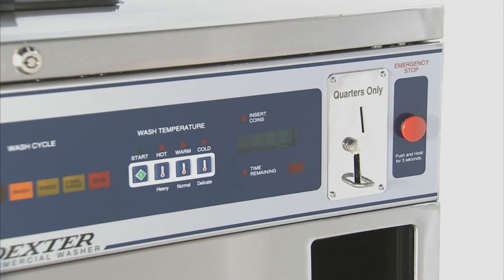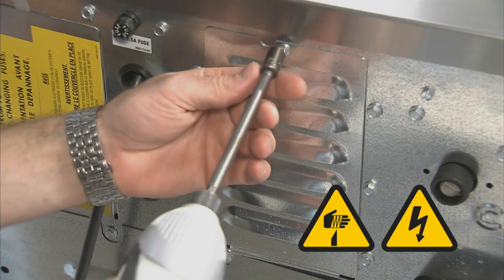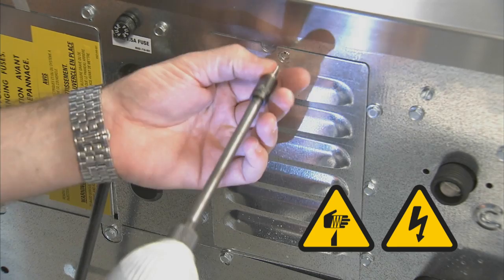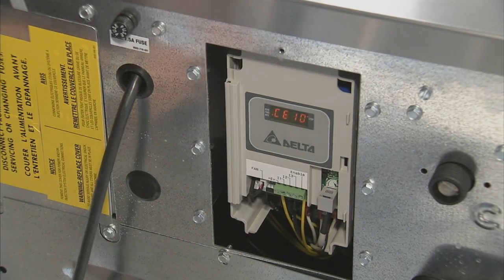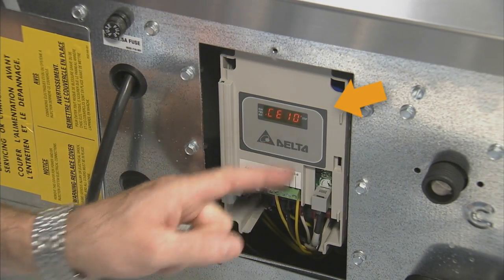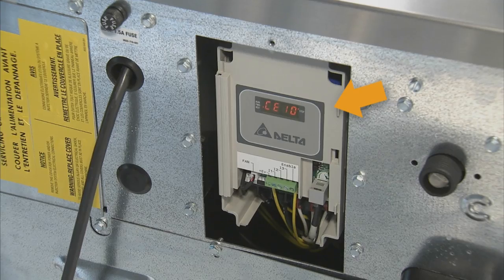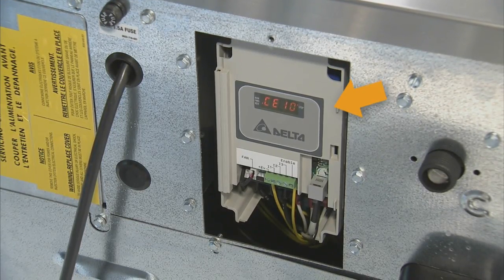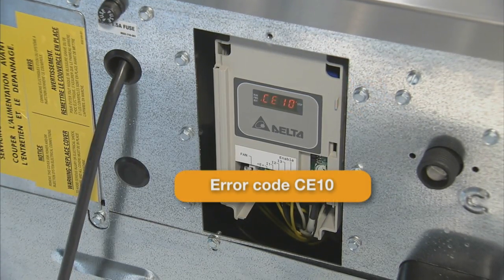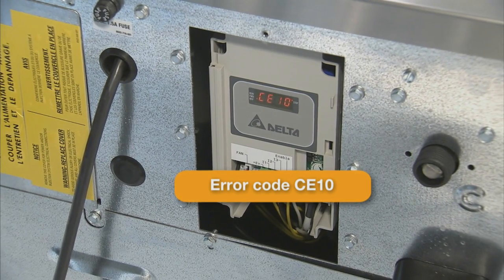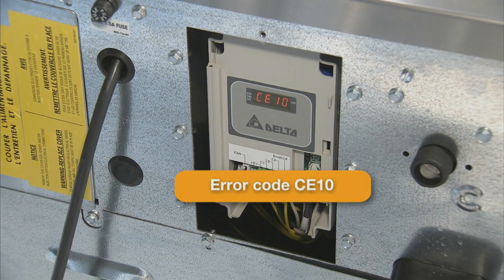When the F13 fault code is present on the front control display of the Dexter washer, the first step to troubleshooting is to access the variable frequency drive, or VFD, display. Using a 5/16 socket and ratchet, remove the screw securing the VFD cover. This allows access to the VFD display. Check the VFD display for error codes. If the error code CE10 is present on the VFD display, use the following steps to troubleshoot the error code.